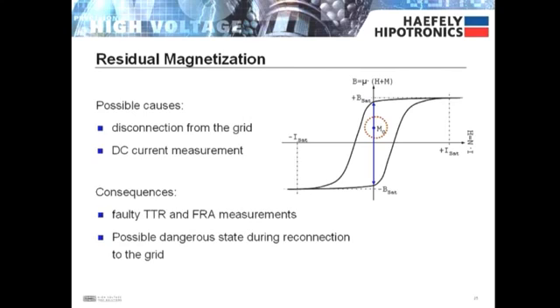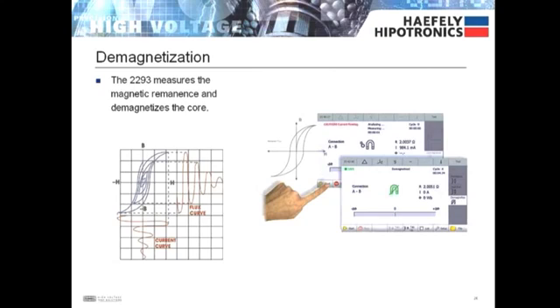This may not be the case if the transformer is disconnected from the grid in the presence of high voltage or if DC current is applied, such as during a resistance measurement. The transformer should be demagnetized to prevent faulty measurements during following turns ratio or frequency response tests and to avoid possible inrush currents when the transformer is reconnected to the grid. The 2293 measures the magnetic remanence and is able to demagnetize the core.